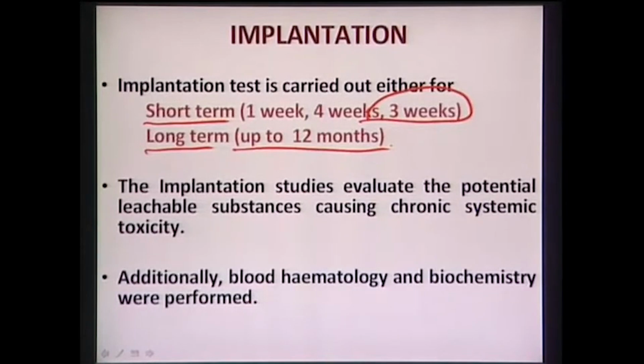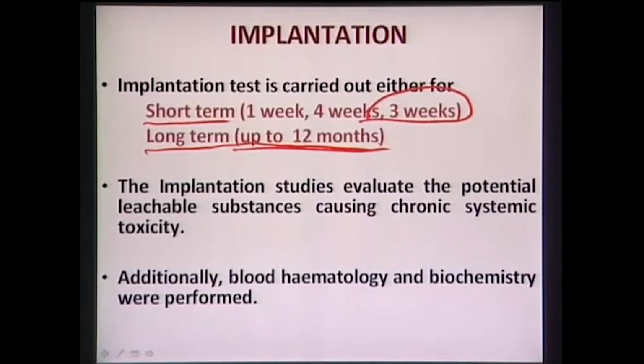Now, why are these two types of tests necessary? If you want to screen a certain biomaterial for whether it is in vivo biocompatible, you can do it for a short term period and a long term period. What happens if some materials undergo some leaching or biodegradation over the long term period? Then that cannot be assessed if you do a short term period like up to 3 weeks or 4 weeks or up to 12 weeks. Therefore, if you do the long term test, then you can be more sure that this material is in vivo biocompatible on a long term basis.